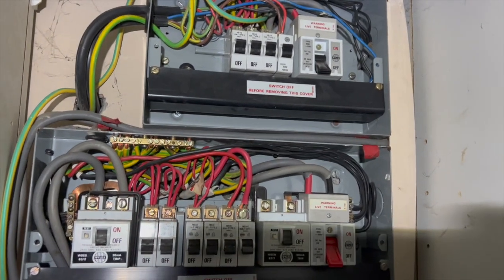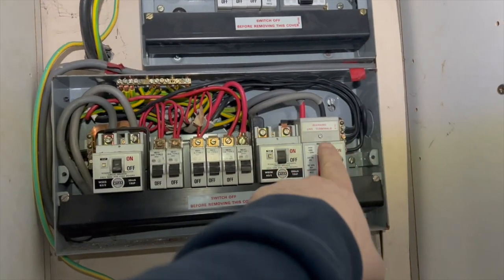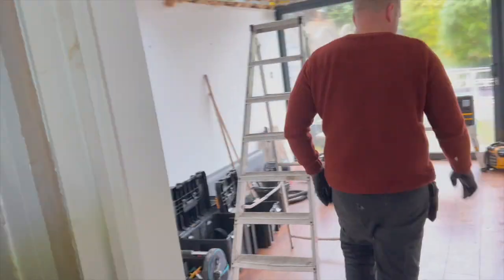So we're just Tuesday morning, just doing this condition report. We're doing a rear extension, and actually moving this fuse board which is going to go from here over to there. We're just doing the condition report to see what's all here. What they've got is they did have an off-peak board which has been converted - this is funky as anything - because the power comes in there, then through the bottom, through this RCD, then fed up there, through there, up to that one. And by the looks of it, all the old storage heaters have been converted because obviously you've got the gas boiler there. And that looks like it's going to be the old extension, the main for the old conservatory.